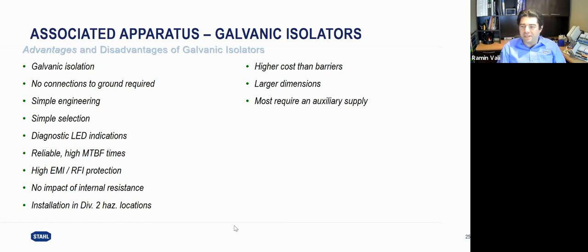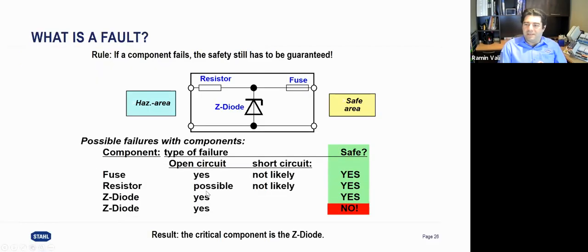Now, system integrators can benefit from other solutions like a DIN rail or power bus, something like that, to connect the power supply to a group of isolators instead of wiring them one by one for the power supply. Now, we learned that these safety barriers prevent the fault from being propagated to the field area. Now, what happens if we have a safety barrier which is faulty?